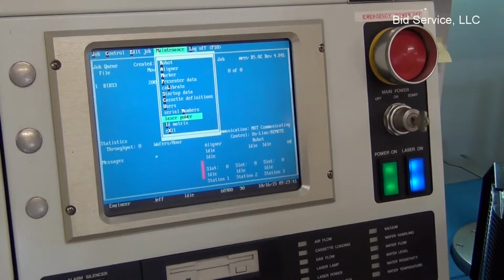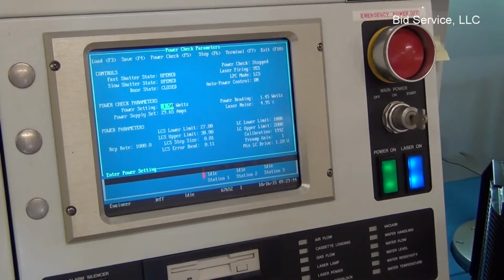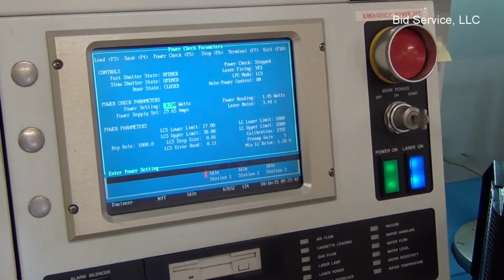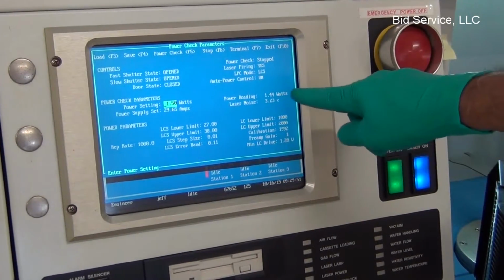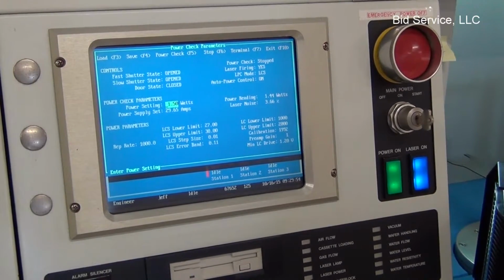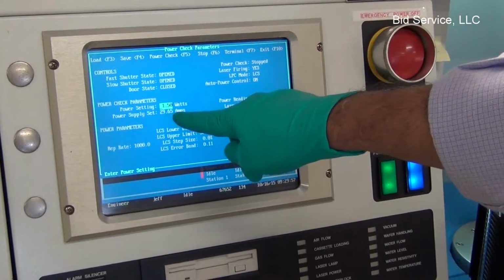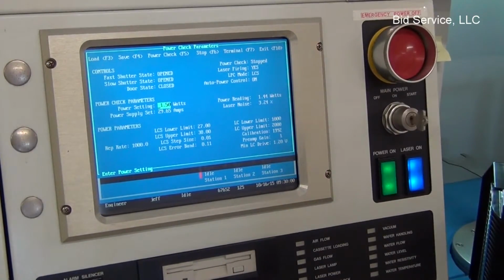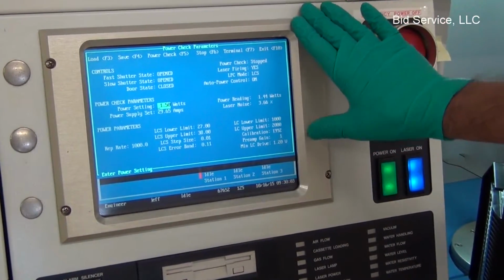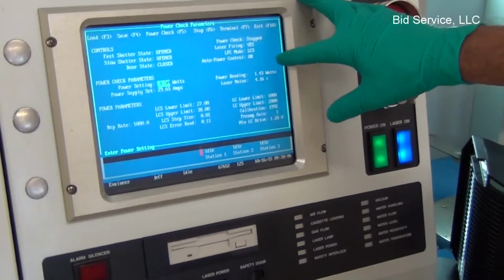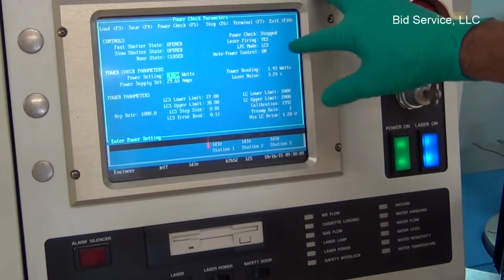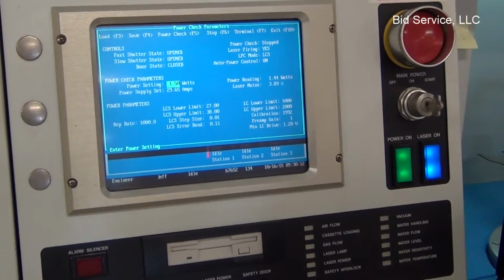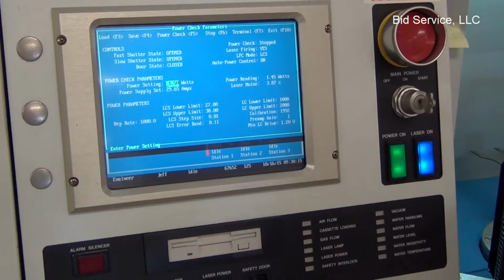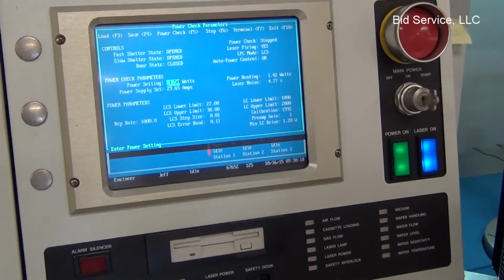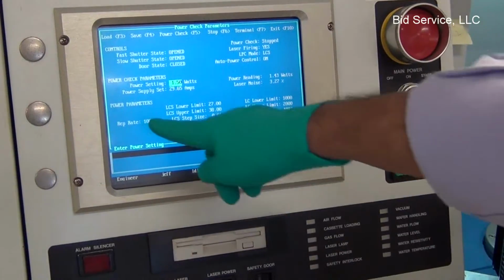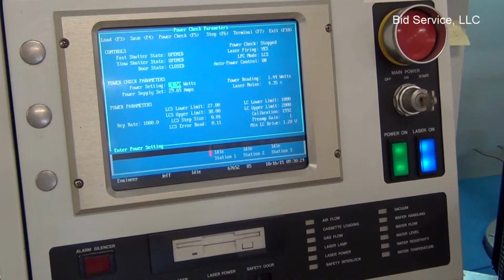Just to demonstrate, I'm going to the laser power screen. Here it is indicating that the power setting is about 1.5 watts, and it is reading 1.5 watts. And the power supply set lamp current is about 29.6 amps. The laser power controller can be operated in different modes, either power control mode or LCS mode, and the details are explained in the user's manual.